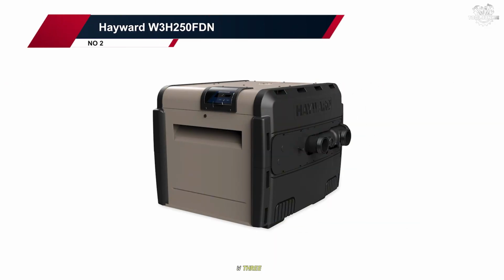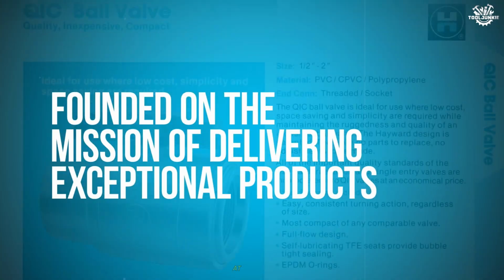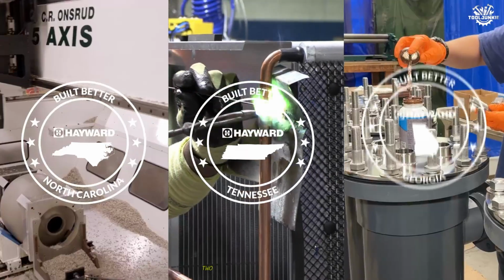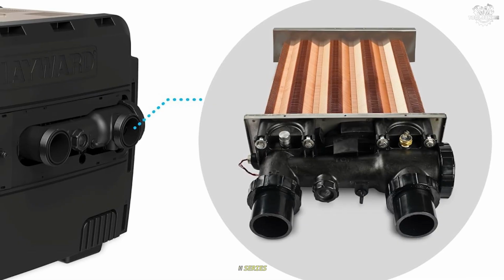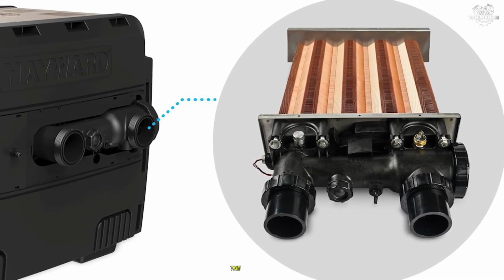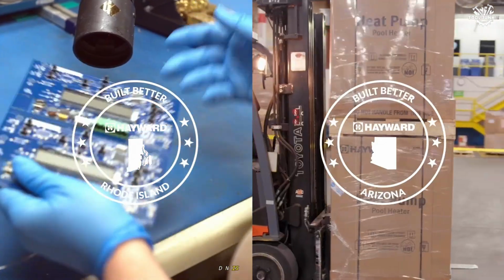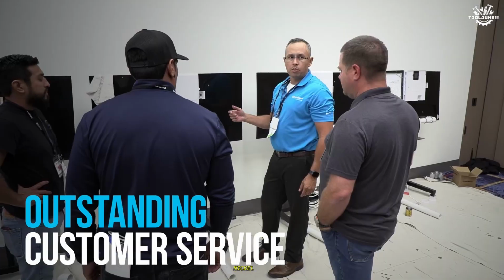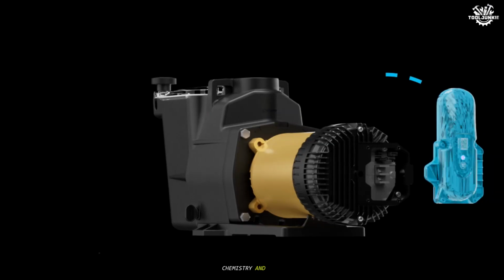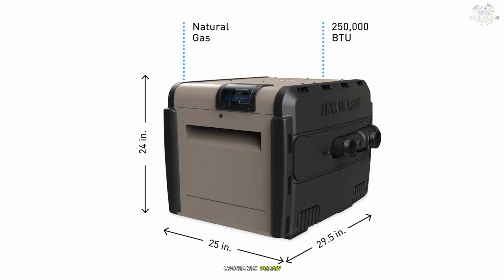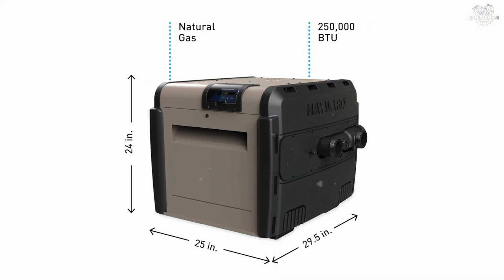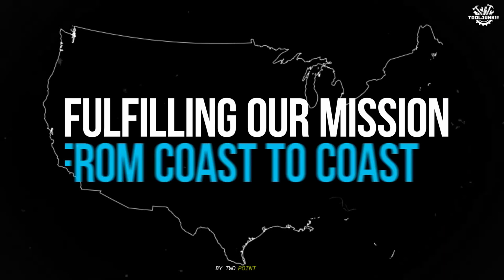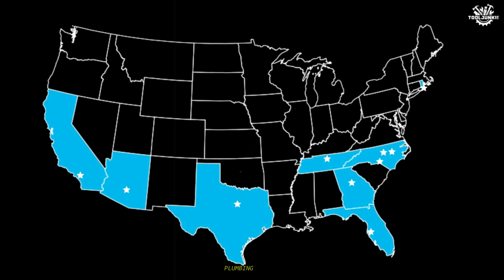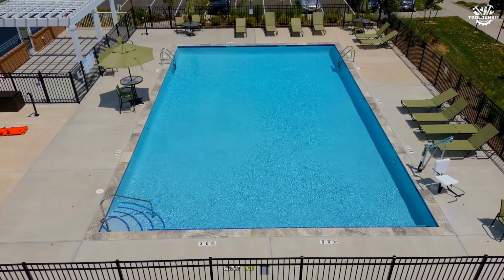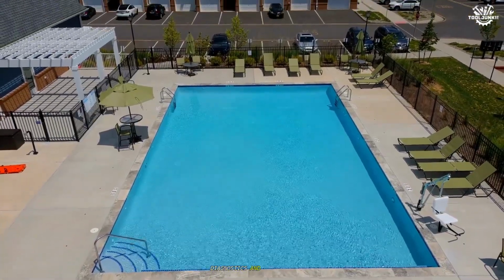2. Hayward W3H250FDN. When fast heat matters, cool morning, party at 5 p.m., gas wins. And Hayward's 250,000 BTU Universal H Series is the entry to that speed-to-heat world. The W3H250FDN is a natural gas, low-NOx unit with a cupro-nickel heat exchanger built to handle aggressive water chemistry and salt systems, and a forced draft combustion design that keeps performance steady regardless of wind. On setup, the flexible 2 inches by 2.5-inch CPVC unions and right-left side plumbing options simplify retrofit installs, while the digital LED control panel streamlines diagnostics and set point control.